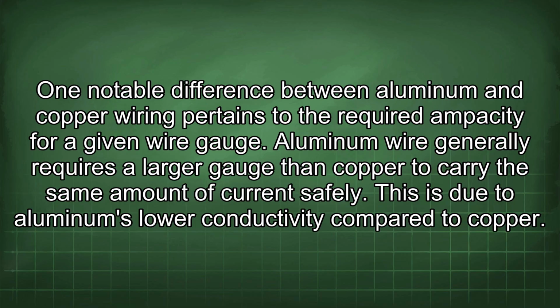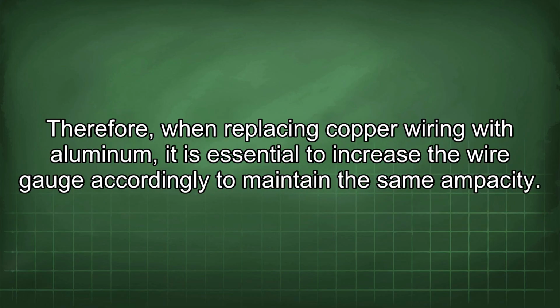One notable difference between aluminum and copper wiring pertains to the required ampacity for a given wire gauge. Aluminum wire generally requires a larger gauge than copper to carry the same amount of current safely. This is due to aluminum's lower conductivity compared to copper.